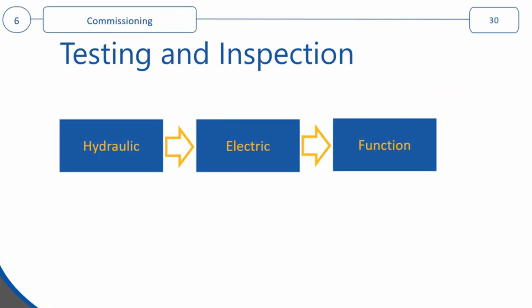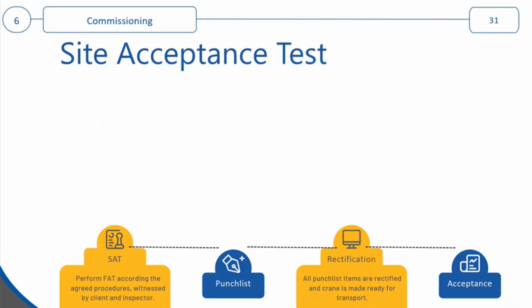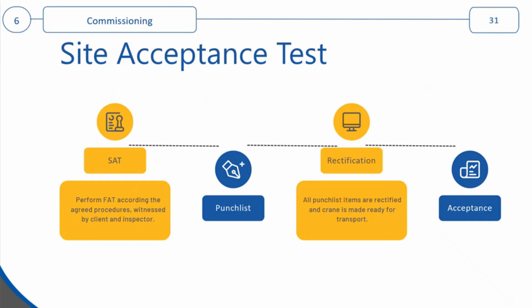Then we do testing and inspection, of course. All systems will be connected and tested. In the end, we will perform a load test as part of the site acceptance test. And this load test requires load test equipment, typically water bags. Make sure that you have them on board and that you have crew that can operate those water bags. It might require rope access, for example.